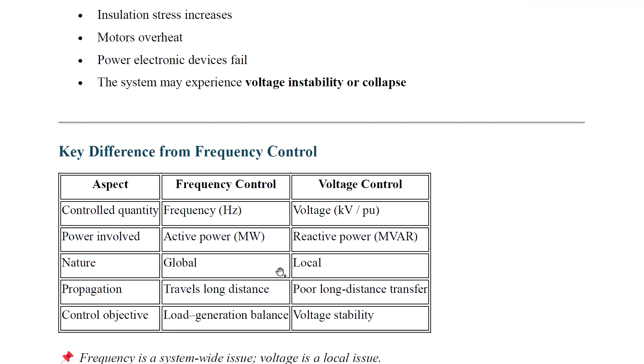What are the main key differences between frequency control and voltage control? If you take the control quantity, in frequency control the control quantity is frequency, in hertz. In voltage control, the control quantity is obviously voltage, that means kilovolt or per unit. Next, the power involved in frequency control is active power. The power involved in voltage control is reactive power, that means MVAR. The nature of frequency control is global control, and voltage control is local control. Next, propagation: frequency control travels a long distance, but voltage control is poor at long distance transfer.